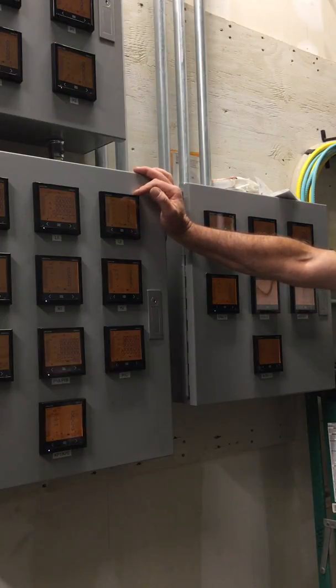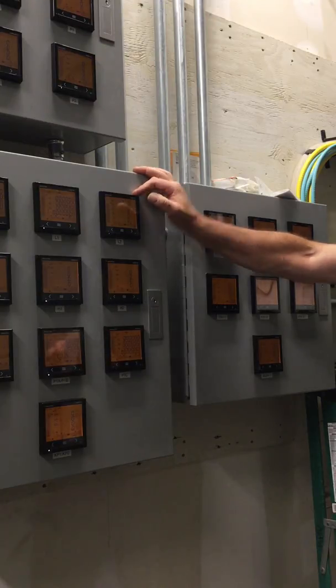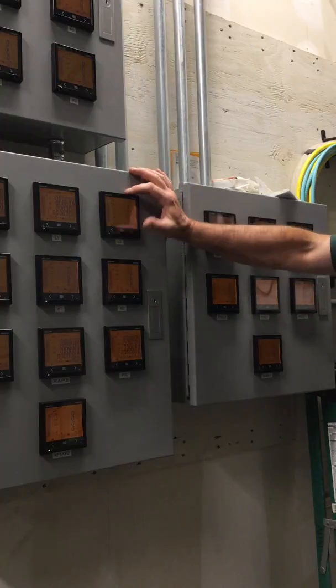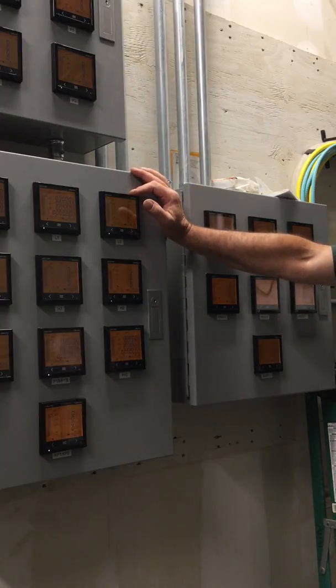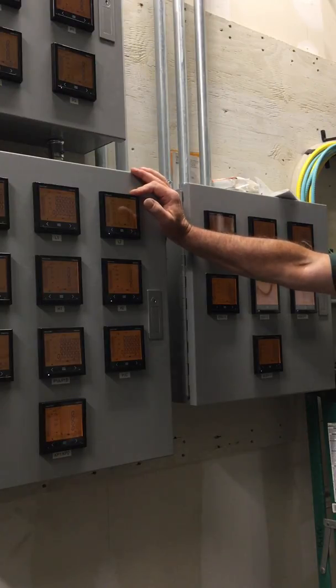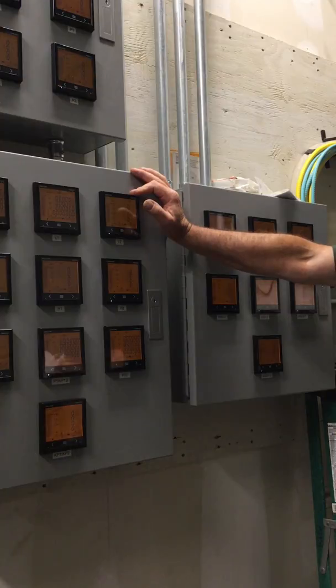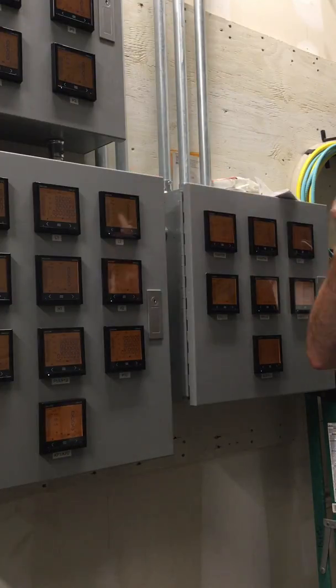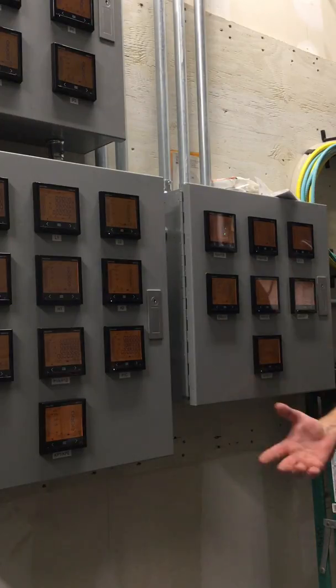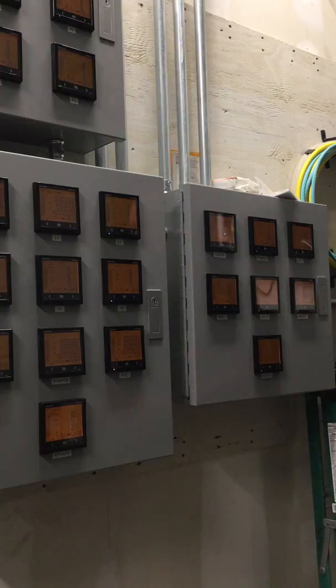Everything's labeled in terms of the accuracy of the CT. They have to be labeled with part number, manufacturer, accuracy, burden, VA. All that information is labeled on the CTs. As years go by, depending on how hot the enclosure is where the CTs are, sometimes the label glue gets a little dry and the label kind of moves down onto the floor somewhere. But right now, they're labeled.